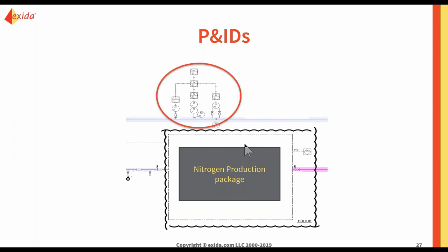For example, right here, you can see there's a cluster of controllers over there. It is doing some kind of flow difference calculations and I don't know what they are actually trying to achieve. When I first saw that, I was thinking maybe they're trying to calculate the flow difference as historian data only. But I've seen in the past in alarm workshops, because alarm workshops have a lot of involvement with the BPCS control system, I know that there should be some kind of trip over there. So it turned out to be true.